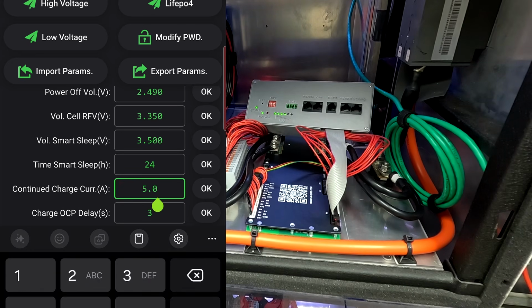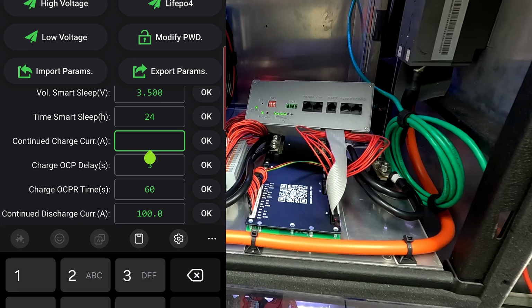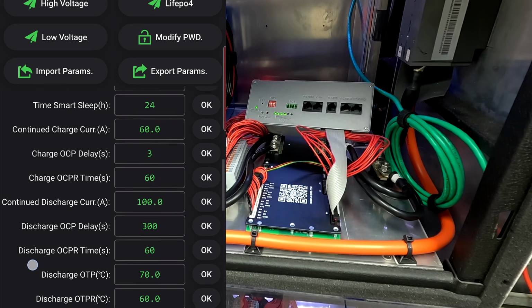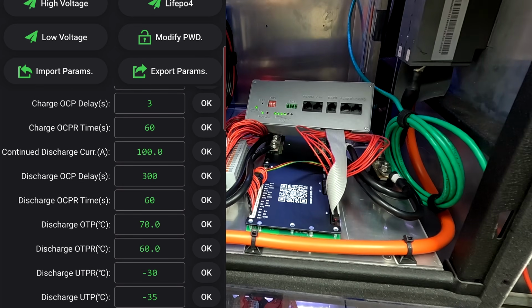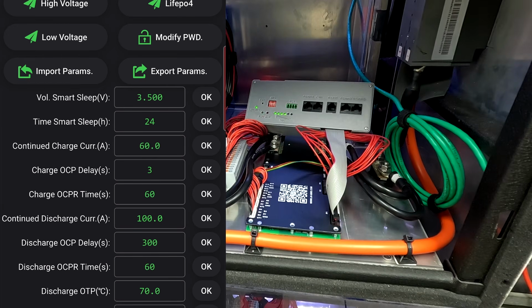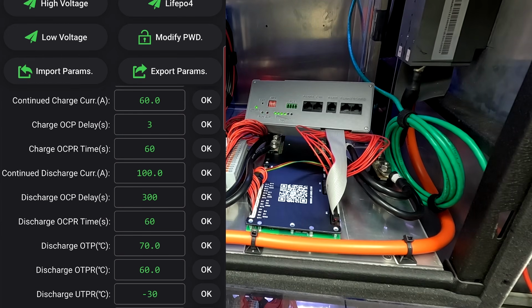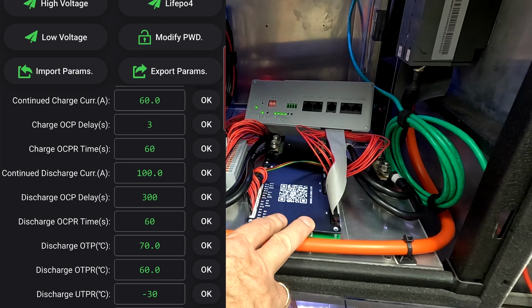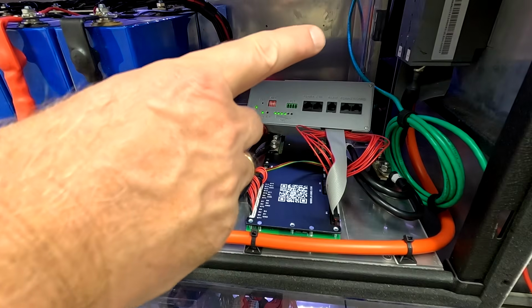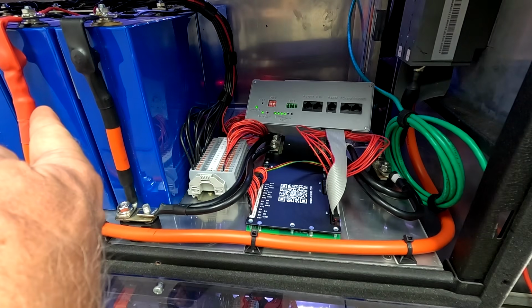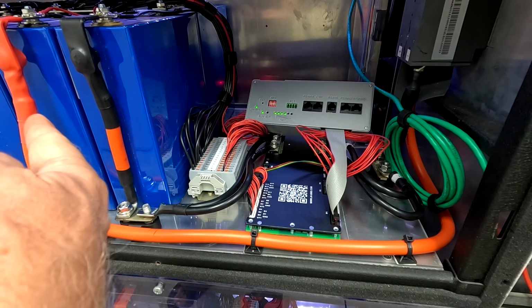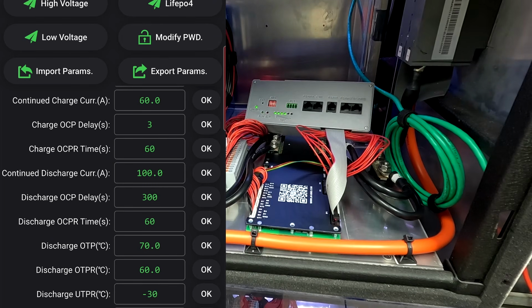Continuous charge current, okay, this needs to be a bit larger, maybe we do 60 amps. Continuous discharging 100, we leave this as it is because we want to do a capacity test on this battery, so we may need a bit more power. Later on I'll set this down to 50 or 60 amps as well. The BMS will be the first point of defense in case we have a high current. It should shut down at 50 or 60 amps, depending what we're setting. Then we've got the breaker with 80 amps, and the fuse here with 150, 200 amps. They should be totally super safe then.